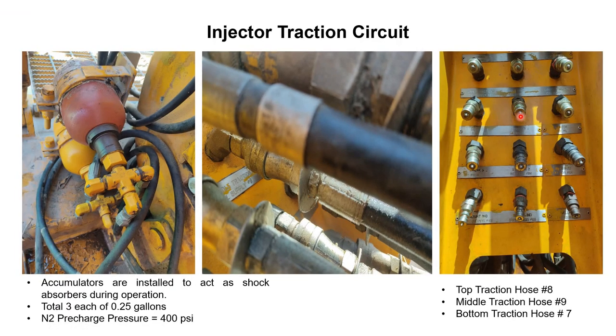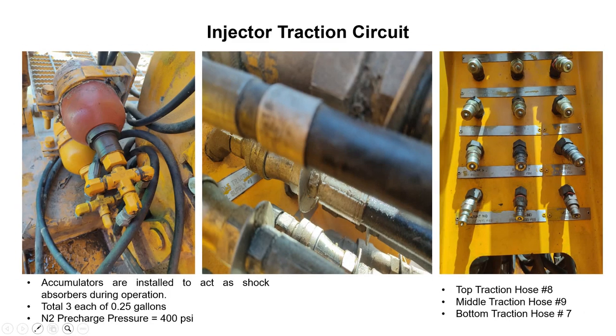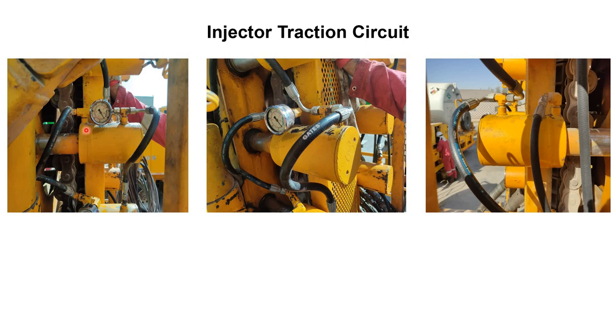We have discussed the middle circuit. At this point, we connect hose number 9. This is the middle traction, so we connect this hose. On the back side, this hose comes to the accumulator and is connected to it. At the accumulator, the flow is divided into two parts. One supply goes to the middle cylinder visible here, and the other supply goes to the second cylinder — the parallel cylinder on the other side — connected on the other side. In this way, the pressure circuit is completed.